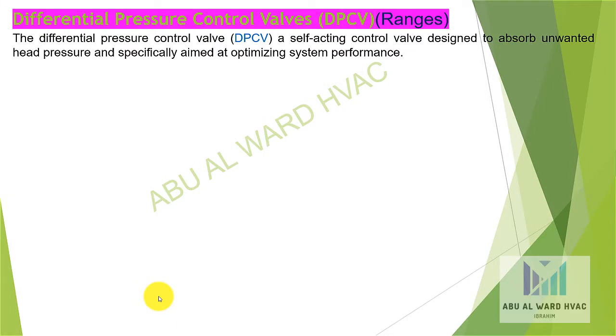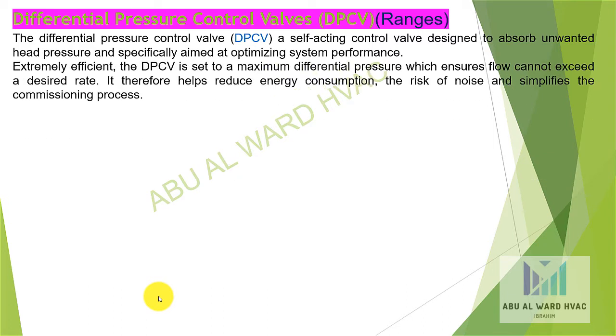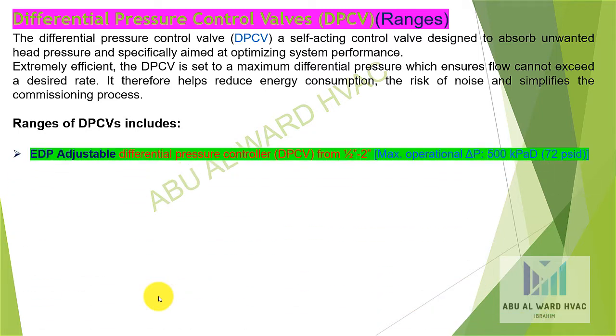The spring force equals the Delta PC. In all DPCVs, the diaphragm is a rolling diaphragm, resulting in a very compact valve design. Depending on the differential pressure control valve selected, Delta PC may be fixed or externally adjustable. The differential pressure control valve is a self-acting control valve designed to absorb unwanted head pressure.